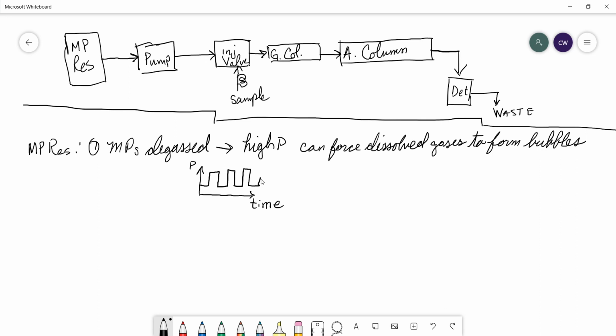Okay? All right, that indicates there's bubbles trapped in the system because it gets low pressure when the bubbles are compressed, and it goes high pressure when the bubble is not compressed. Okay? And in order for the chromatographic separation to be efficient, we need to make sure that our pressures are staying constant. So this is a bad thing.